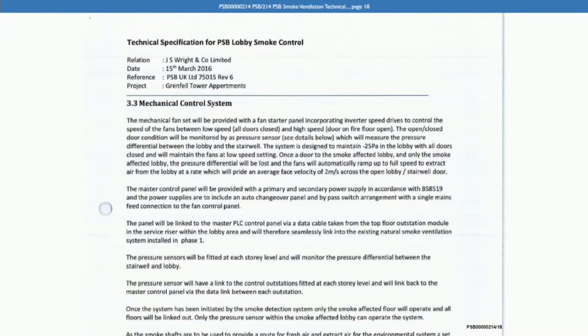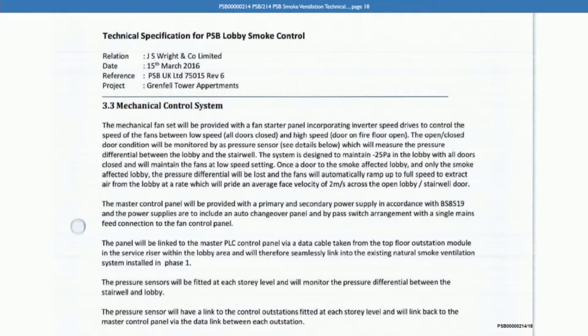And if we go to section 3.3 of the technical submission again, so this is PSB 50214, page 18. Again, you've mentioned this before, but if we pick it up under that section 3.3 mechanical control system, four lines down, in the middle of that line it says the system is designed to maintain minus 25 pascals in the lobby with all doors closed and will maintain the fans at low speed setting. Once a door to the smoke affected lobby, and only the smoke affected lobby, I think that should then read, is opened, the pressure differential will be lost and the fans will automatically ramp up to full speed to extract air from the lobby at a rate which will provide an average face velocity of 2 metres per second across the open lobby stairwell door.